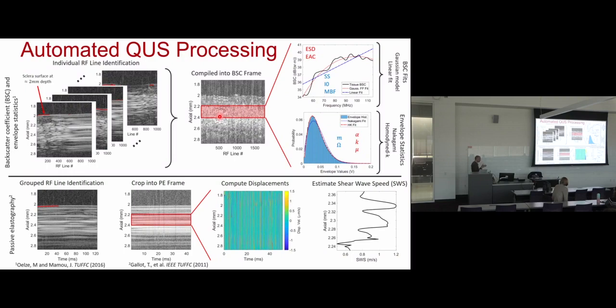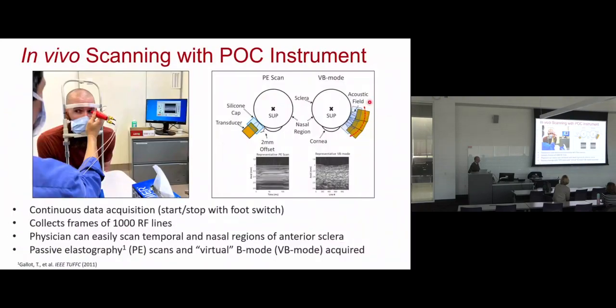It's pulsing at what we call a PRF, a pulse repetition frequency. So there is a clock that says pulse, pulse, pulse, pulse very regularly. And then we record with a buffer and send it to the computer. So this is line number. So how many lines we acquired, and between two lines, I think we have an 8 kilohertz PRF. So it's 1 divided by 8,000 seconds between two lines. The top scan, what we call the virtual B mode, or the scan we use for the BSC, we ask the clinician to move by himself, and we have no special information about how much is moved. And that creates this.